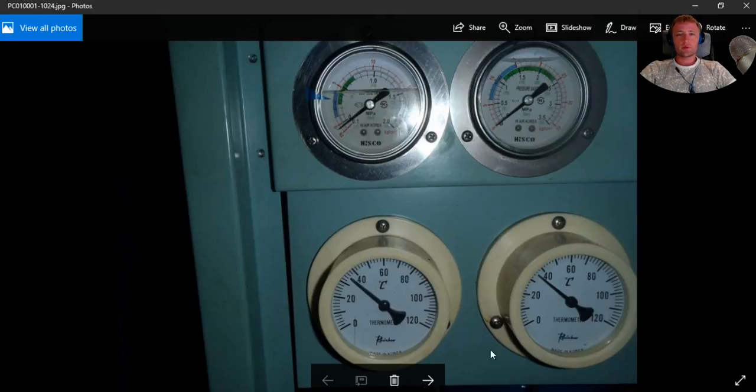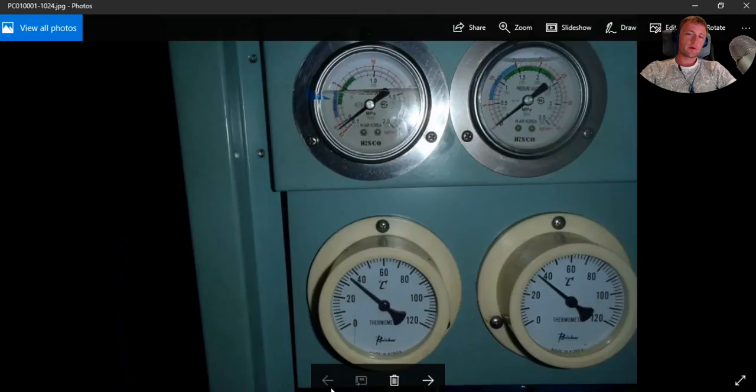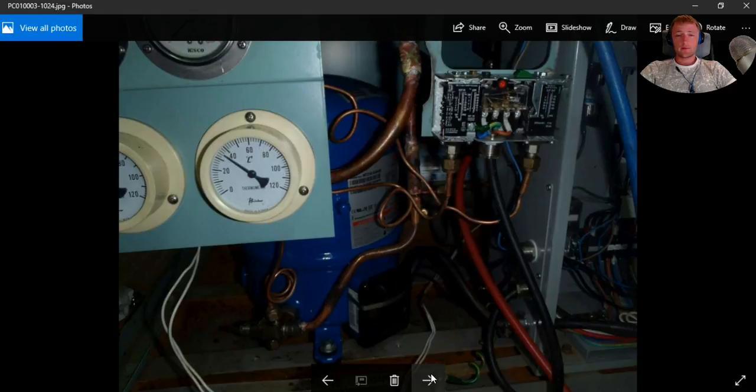Also you have temperature indicators here, and let's see. And after this test, as you can see, the vacuum is high enough, you can fill the oil. You can fill the oil here inside, and then you can fill the system with freon. The quantity for each system is specified. Okay, you cannot put whatever quantity you want.